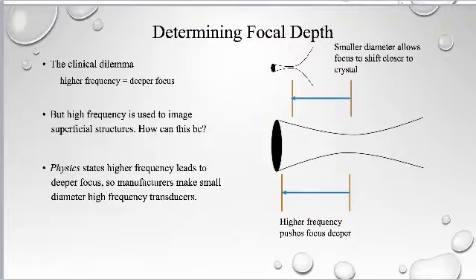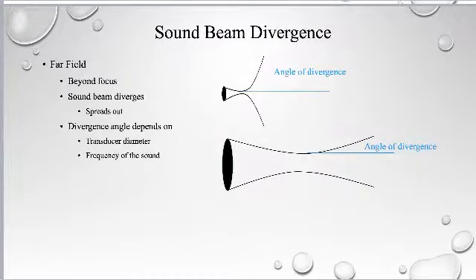Okay. All right. Sound beam divergence. We talked a lot about the focusing in the near field. Beyond the near field, the far field, the sound beam diverges, and the angle of the divergence depends on the transducer diameter and the frequency of the sound, coincidentally. Same thing as everything else depends on, right? So the angle of the divergence, and you can see I've kind of measured these angles of divergence. When you have a bigger crystal diameter, that angle of divergence is much, much less than when you have a small crystal diameter. We good with that?